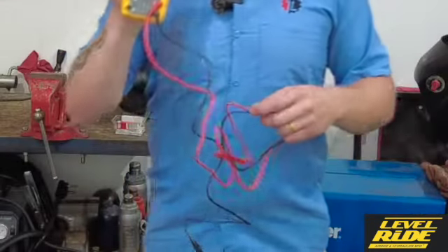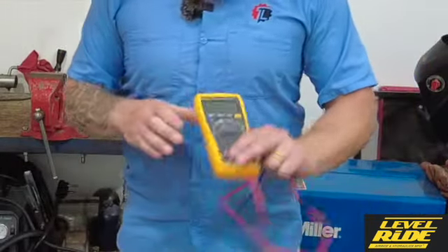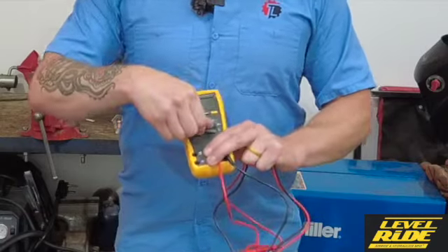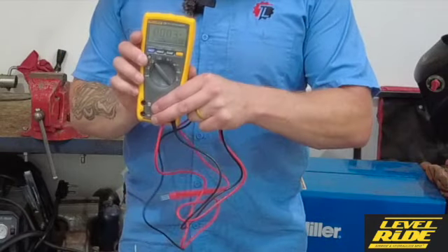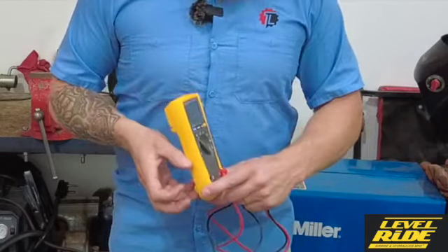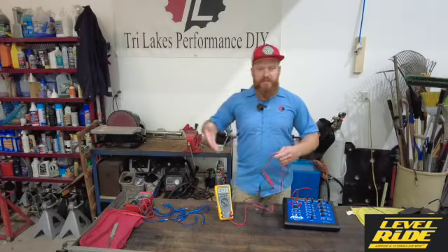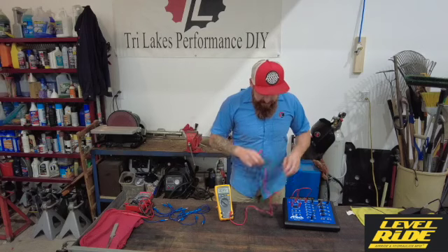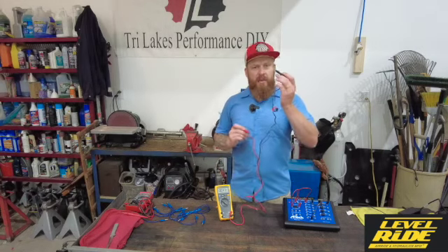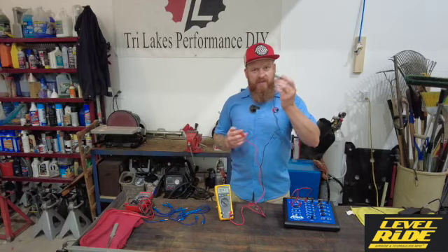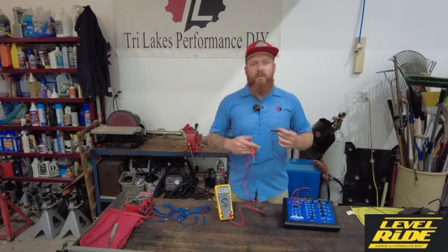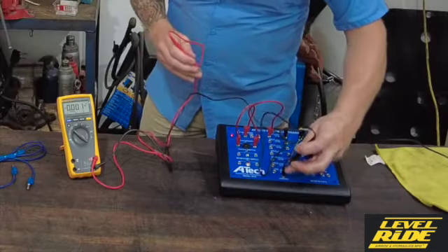Voltage drop is easily measured with a multimeter. What we want to do is set this to volts DC, and we're going to commence checking voltage across the circuit. We always put the black or common lead towards the ground side of the circuit, and the red lead towards the positive side.